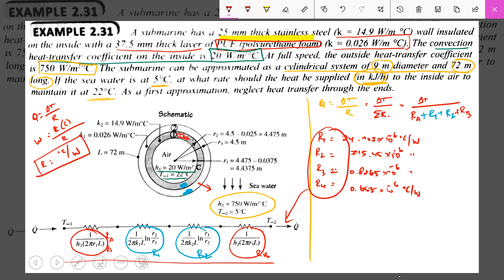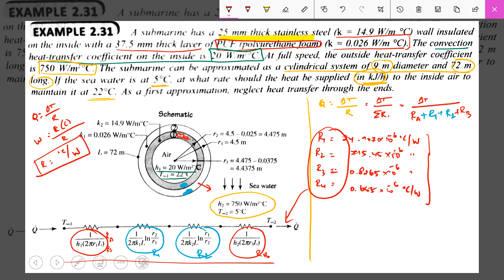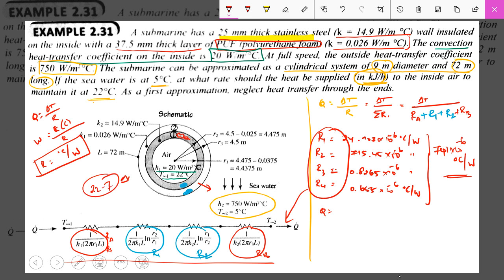By summation of all the resistances, you finally get a total resistance of 741 into 10 to the power of minus 6 degree Celsius per Watt. Delta T is the difference between the two extreme temperatures: the outer side is 5 degree Celsius and the inner side is 22 degree Celsius, so delta T equals 22 minus 5, which is 17 degree Celsius.